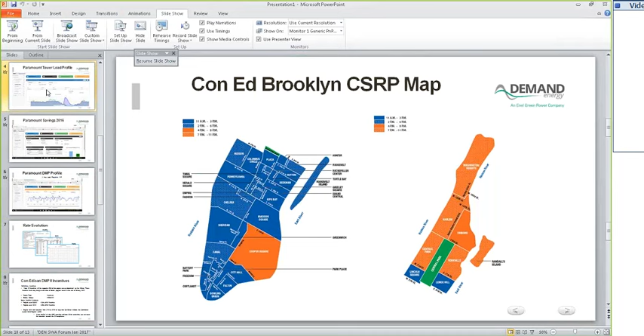Typically it's more the energy. It's a 400 kilowatt hour system, right, and fundamentally it takes about 5 to 6 hours to refill that back up. You can see that in the profile up there. We can get away with this because we're not getting hit for demand charges, but for efficiencies, that profile is running about 100 kW. You can see how it slopes out, taking about 5 hours, basically from midnight till 5 a.m.